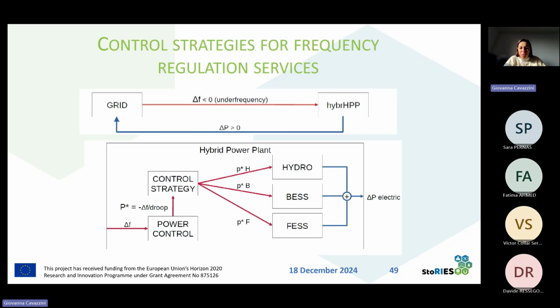But in a hybrid power plant like the one I was mentioning, proper control strategies can be put in place to react to an event of frequency variation from the grid. So as you can see in this scheme, if the grid is suffering an under-frequency or over-frequency event, this will require the hybrid power plant to provide a certain power ramp signal up or down, depending on the needs.